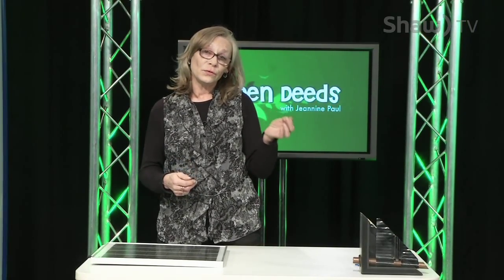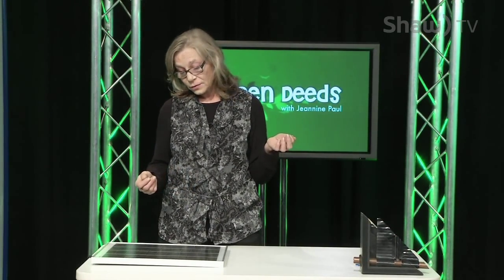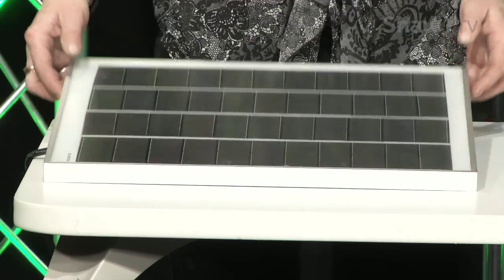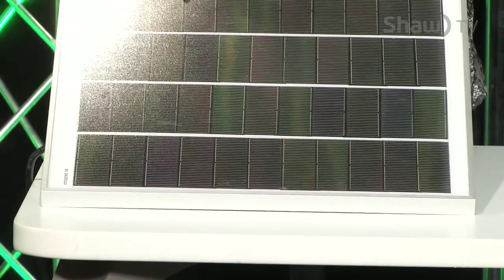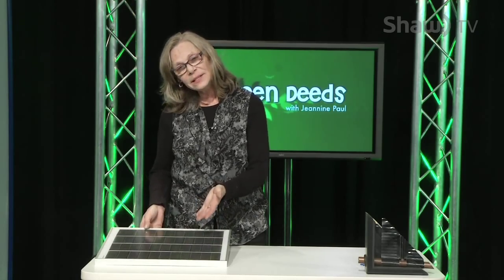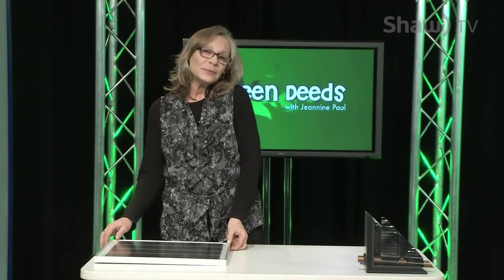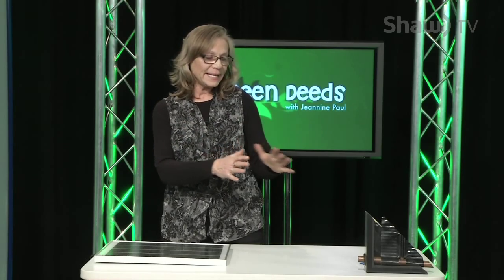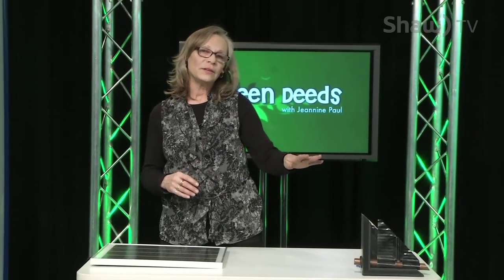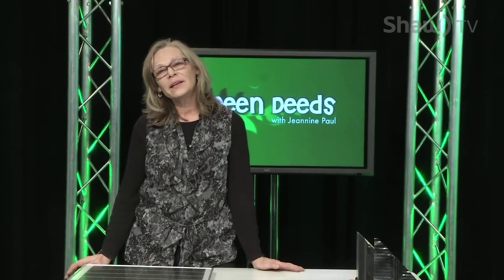You can run that pump through regular electricity from the house, or you can use, like what Jared has, a simple photovoltaic panel. This is nice because when it's really hot and there's a lot of heat in the thermal panel, it forces the pump to run at full speed. If it's the end of the day or dimmer with only a little heat, it causes the pump, in a variable speed way, to go at a low rate. So it's self-regulating, and that's one of the things we love about solar.